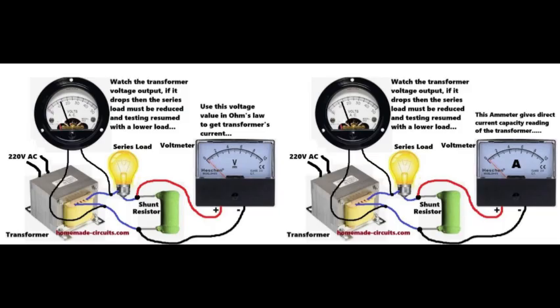What idea will we use? We will use the concept like this. We connect a low-value shunt resistor at the output of the transformer. Then we connect an ammeter across this shunt to measure current. Then we slowly load the transformer and see how much current it gives. We keep watching voltage drop, current, and heat. When the transformer starts heating too much or voltage starts dropping badly, then we assume that we reached its maximum safe current limit. Let us say we have a 12 volts transformer. Any voltage is okay, just an example.